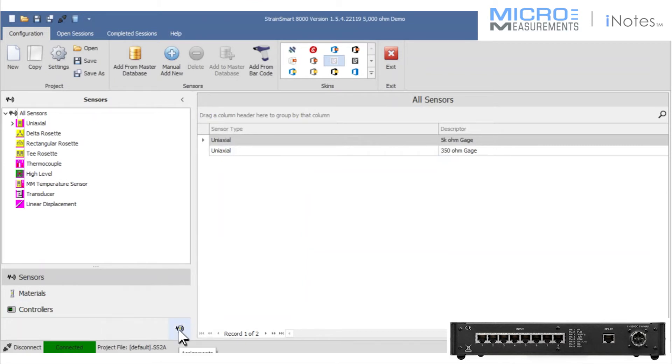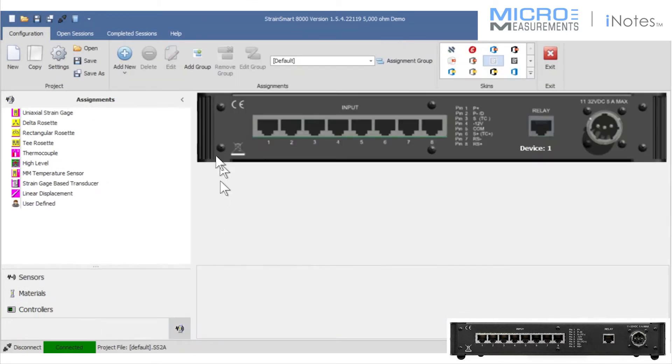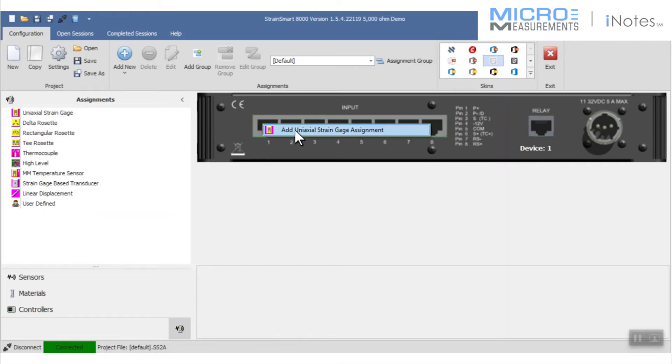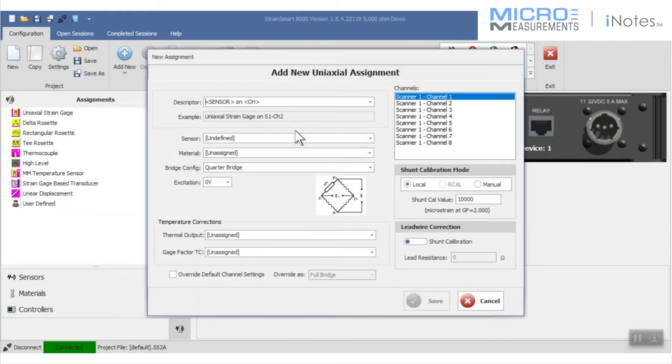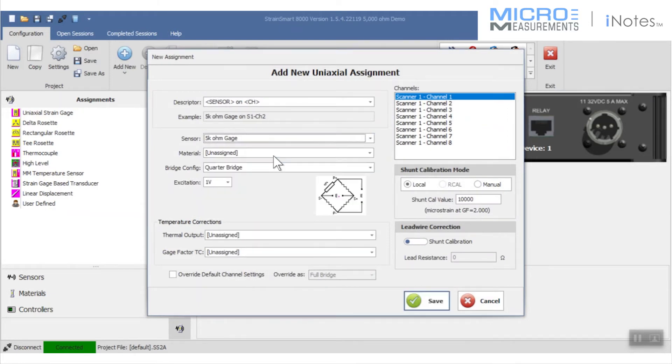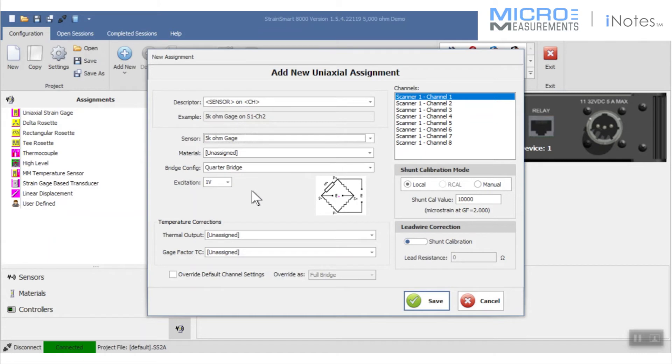I get the green light and now I'm going to tie the sensors that I've created with each channel. On the first channel, I have a whole lot of choices going on here. Most importantly, I'm going to choose the 5,000 ohm strain gauge to be on channel one as a quarter bridge with a one volt excitation.